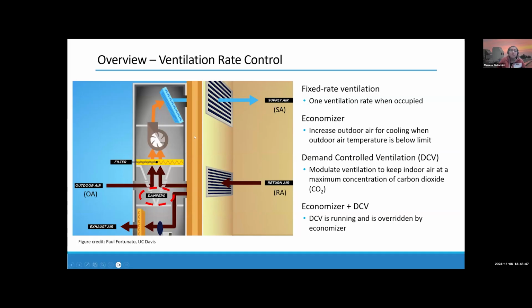A very common technology in California is an economizer. So basically what that does is when the outside air is cold and we call for cooling in the building, we increase outdoor air to like 100% of the supply airflow rate, and we cool the building essentially for free cooling. And the final technology is demand control ventilation, where we monitor indoor carbon dioxide concentration as we're all exhaling.